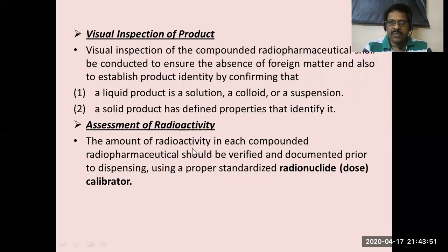Assessment of radioactivity is one quality control parameter. The amount of radioactivity in each compound in the radiopharmaceutical should be verified and documented prior to dispensing using a proper standardized radionuclide dose calibrator.